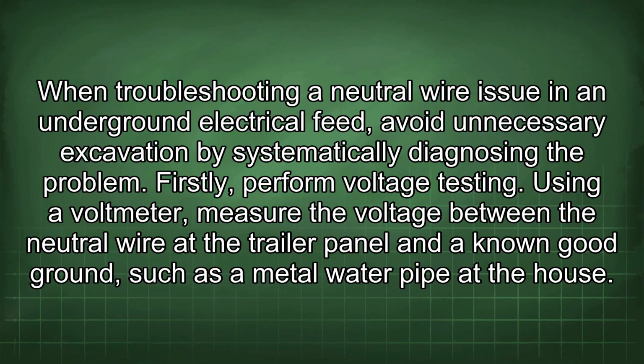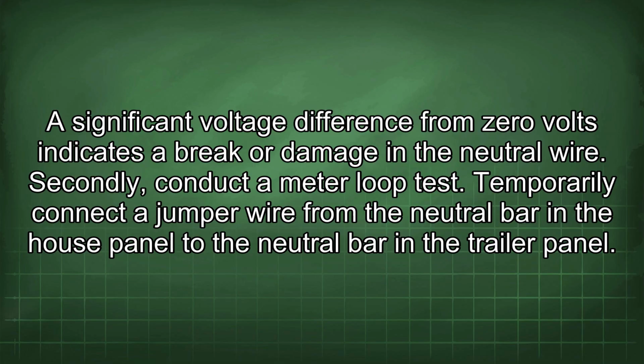When troubleshooting a neutral wire issue in an underground electrical feed, avoid unnecessary excavation by systematically diagnosing the problem. Firstly, perform voltage testing. Using a voltmeter, measure the voltage between the neutral wire at the trailer panel and a known good ground, such as a metal water pipe at the house. A significant voltage difference from 0 volts indicates a break or damage in the neutral wire.